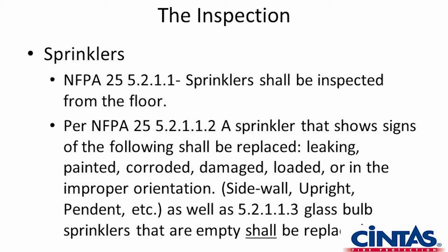Last, talking about glass bulb sprinklers. If you've looked in one of your facilities and seen a red or a green colored liquid in the glass bulb, the coloring is just an indicator of what temperature range that sprinkler head is. In the majority of your facilities, you're going to see a red colored liquid. That's a sprinkler head that discharges at 155 degrees. Inside that glass bulb, there will be a little air bubble. The way the glass bulb is designed, as heat builds up around the sprinkler head to the predetermined temperature, the air bubble expands, there's nowhere for it to go, and so it shatters the bulb.